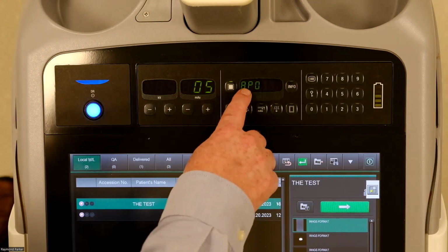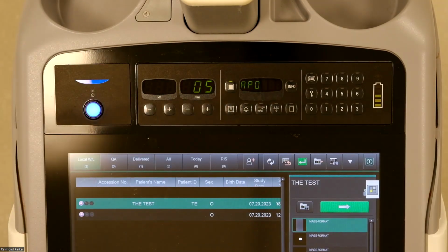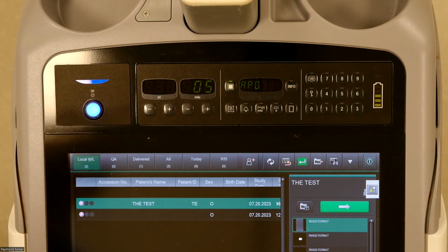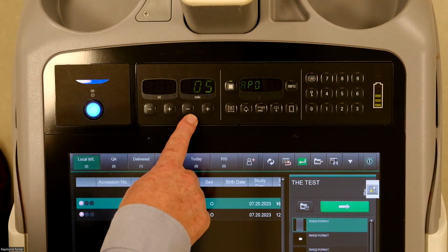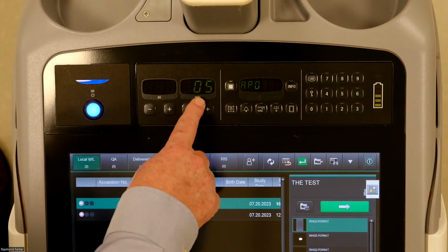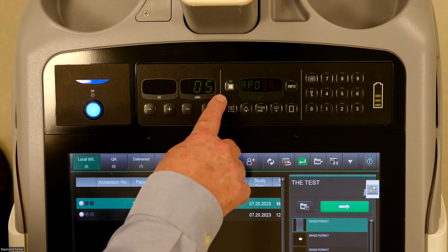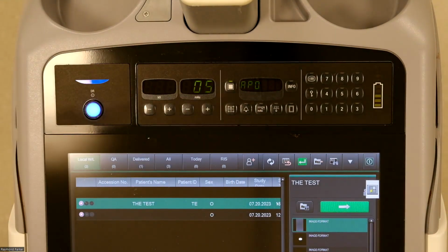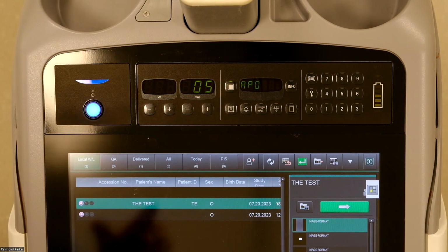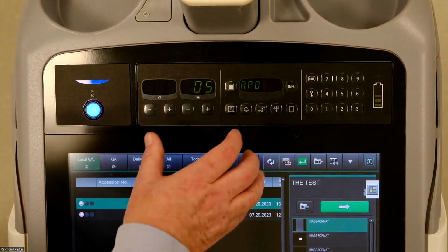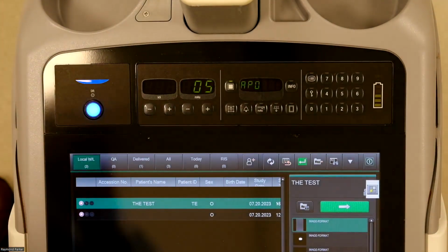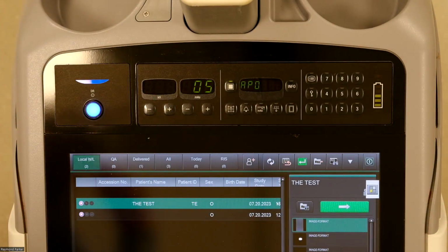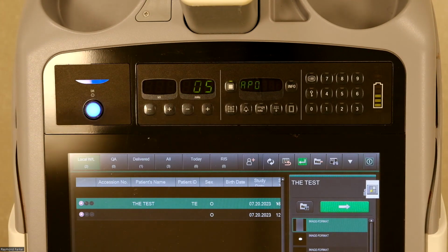Auto power off, APO, that is one that I strongly suggest any applications does verify is set up. That auto power off in this instance would terminate or shut down the system at 5 minutes. And when I say system, the FDX console is separate from the portable. So in this auto power off, all it's doing is dropping the portable unit into kind of a sleep mode or in a power off.